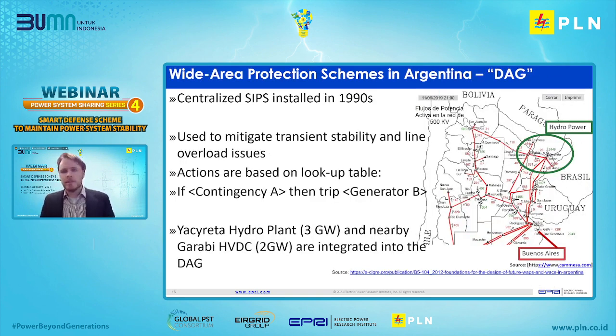This is probably an older example from Argentina, where they installed a defense scheme in the 90s. In this case, there were a lot of transient stability and overload risks. They have a lot of hydropower in the northeast of the country, so there's a 3 gigawatt hydro plant and a 2 gigawatt HVDC link in this area. But most of the load is in the middle of the country around Buenos Aires, highlighted in the map. This is a programmable logic implemented at the substation level, with multiple logic definitions for if this contingency happens, then a generator is tripped or triggered to run back.